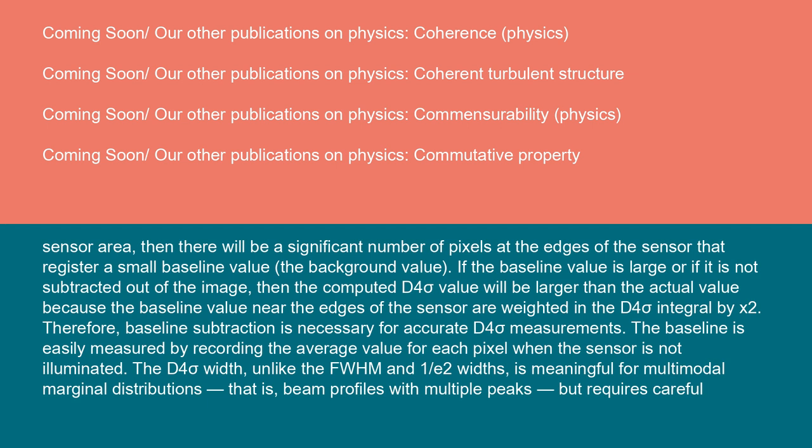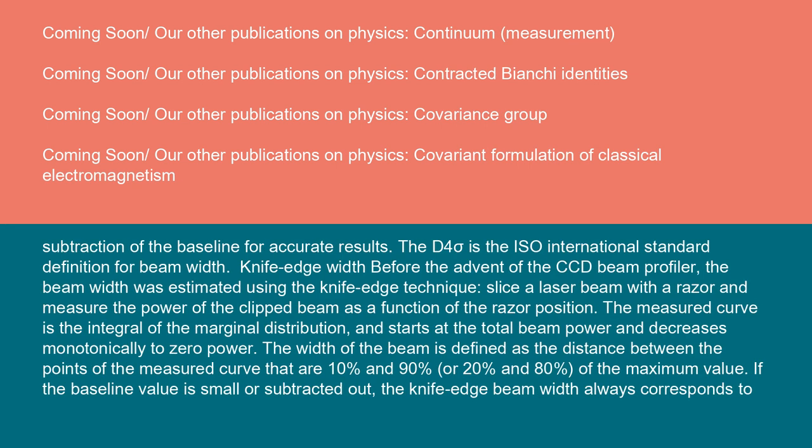Therefore, baseline subtraction is necessary for accurate D4 sigma measurements. The baseline is easily measured by recording the average value for each pixel when the sensor is not illuminated. The D4 sigma width, unlike the FWHM and 1/e² widths, is meaningful for multimodal marginal distributions, that is beam profiles with multiple peaks, but requires careful subtraction of the baseline for accurate results. The D4 sigma is the ISO international standard definition for beam width.